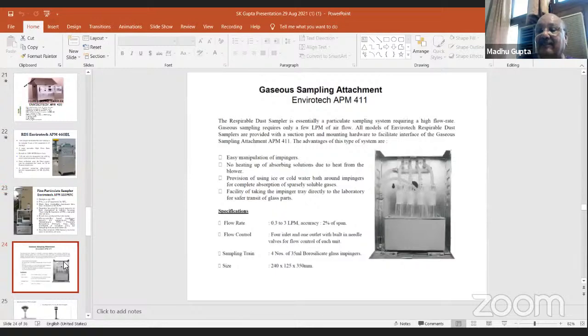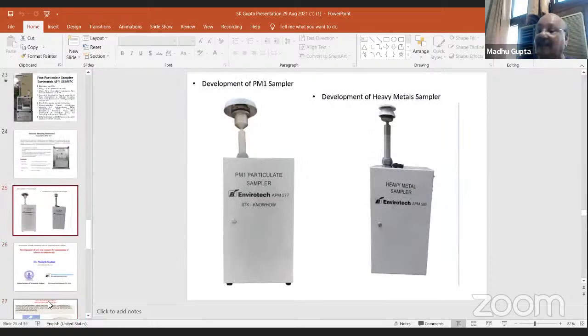These are the gaseous sampling attachments which I mentioned, that gases can be measured by simple wet chemistry methods. These are impingers. In impingers, you put a reagent and absorb a particular gas from the atmosphere, and by analysing that, you can measure gaseous pollutants. Now, PM1 is also becoming important, that is, fine dust and then ultra fine dust. So we developed this ultra fine particulate sampler with know-how from IIT Kanpur, and about 100 pieces of this sampler are in use with various educational and research institutions, collecting data. The Government of India, CPCB, is also working to revise the National Ambient Air Quality Standards by next year. By that time, a lot of data will be collected on PM1, and maybe this parameter will also get included in the National Ambient Air Quality Standards.